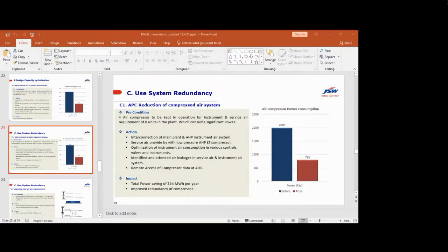Again, part C is use of system redundancy. For the APC reduction of the compressed air system, we have 8 air compressors: 4 instrument air compressors and 4 service air compressors. We did the interconnection of the main plant and ash handling instrument air compressors. The instrument air compressor of the ash handling is of lower capacity, so we stopped the 500 kilowatt big compressor and tried to cater the requirement with the small instrument air compressor, and service air provided with low air pressure.